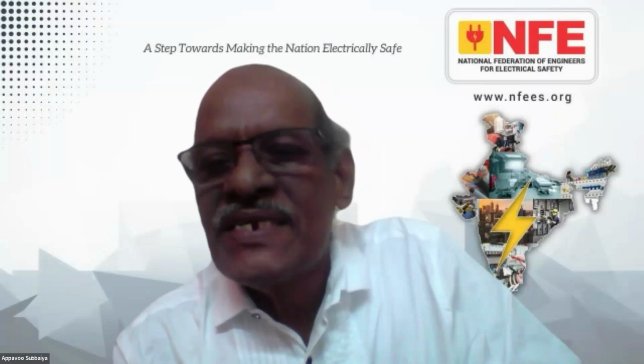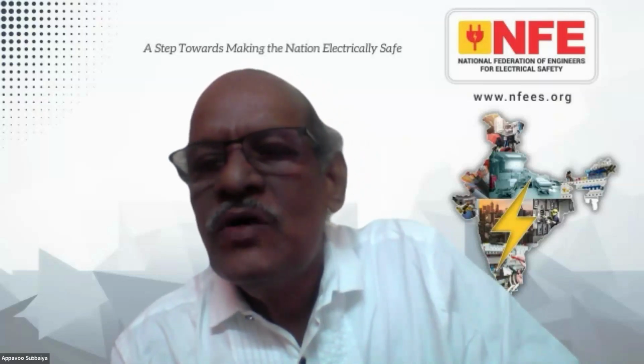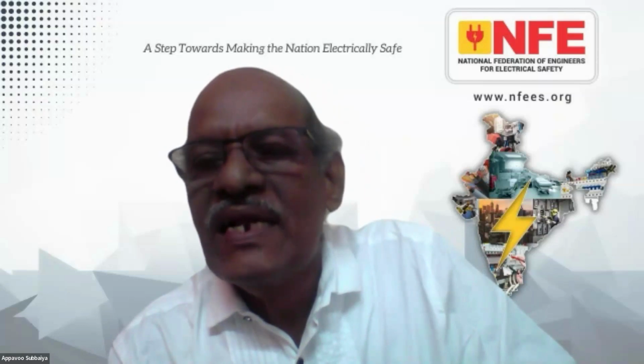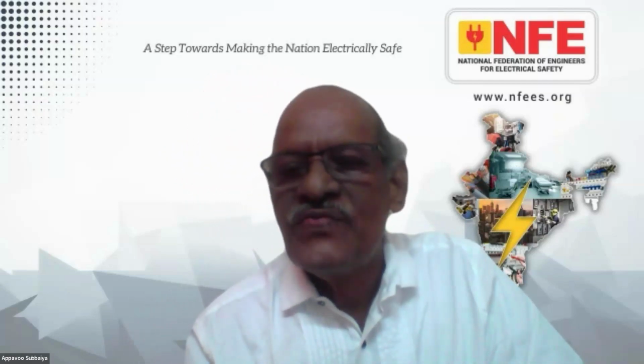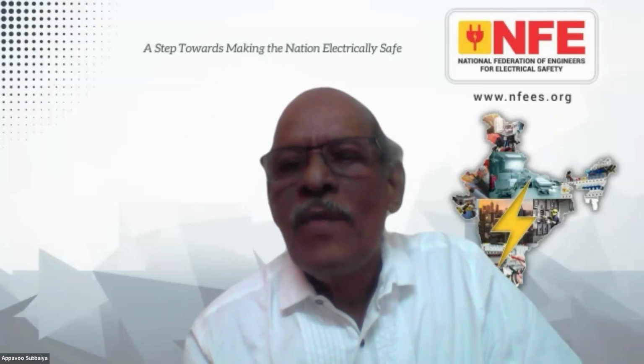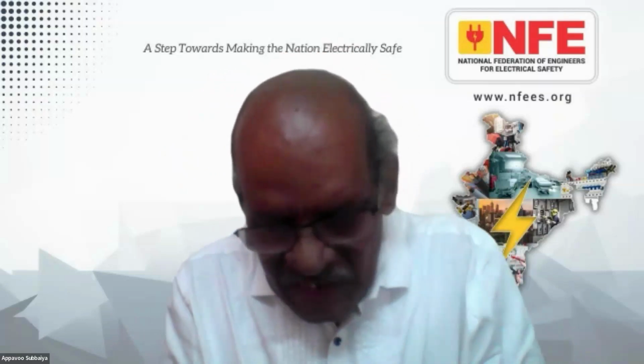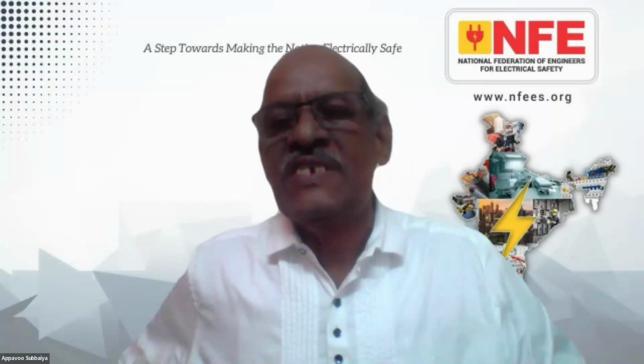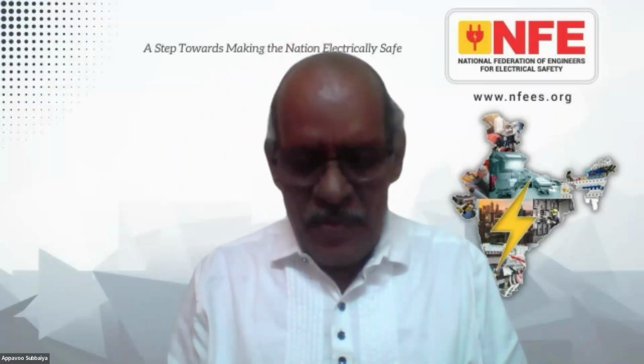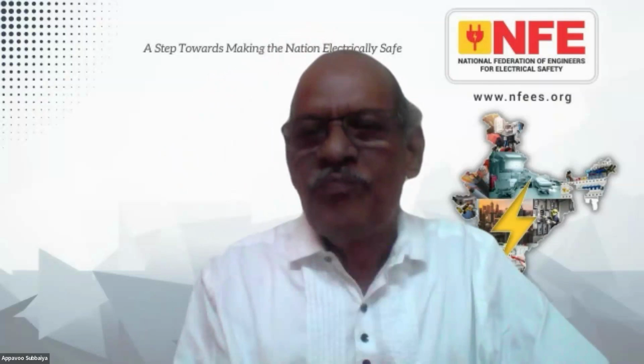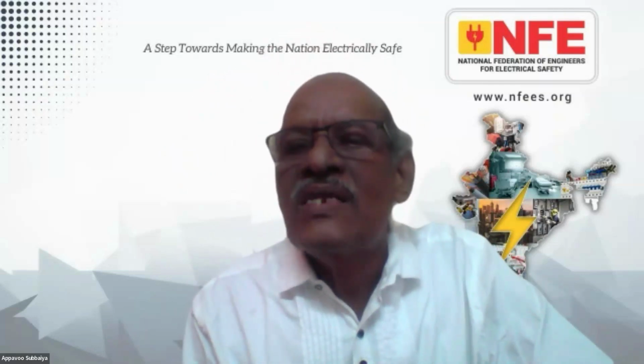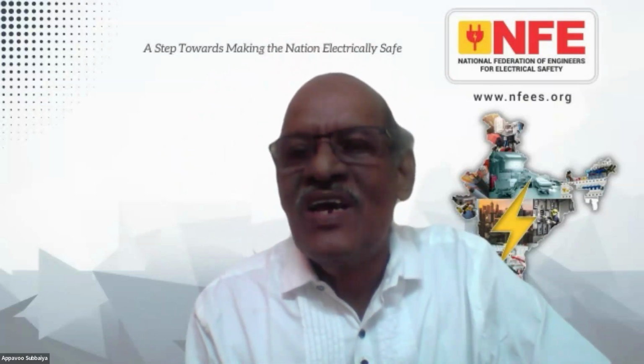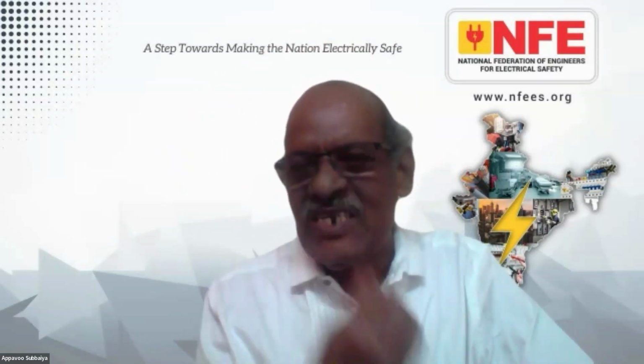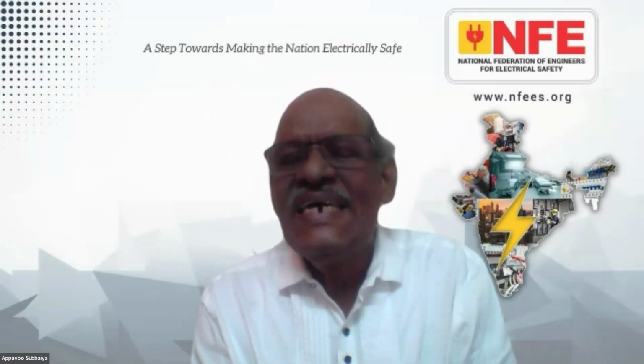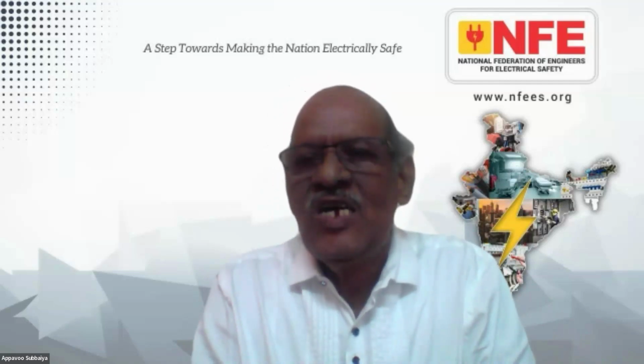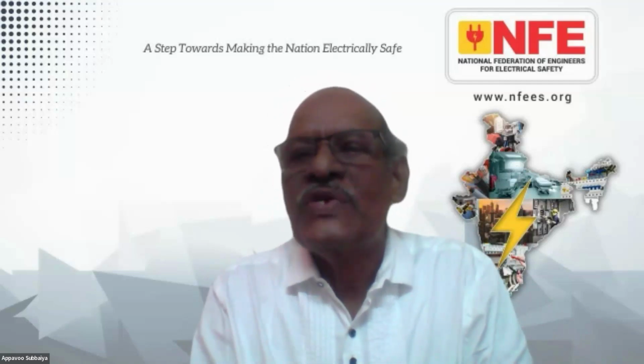Another question is from Magesh Rane. What will be the voltage between neutral and earth in all electrical and electronic devices? There are no standards for this. You just observe the noise mitigation. There is a PowerPoint presentation on our website. Please go through it. The referencing is important. We don't use earthing or several earth electrodes in airships or rockets or even hospital operation theaters. So earthing here is to have a proper reference for neutral and earth.